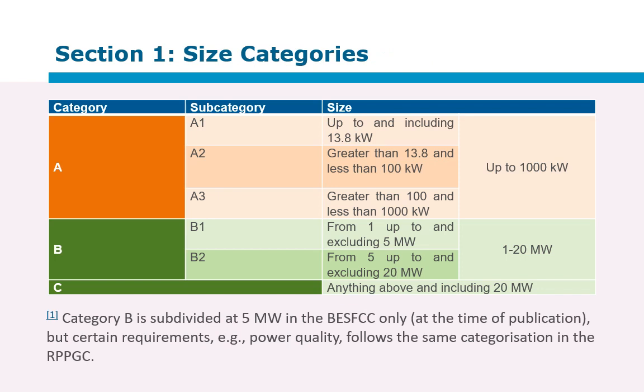Next are the size categories as defined in the grid code for renewable power plants. Category A, up to 1 megawatt, is covered by the standard SSEG processes covered in previous trainings. Many of the technical requirements are dealt with in the NRS 097-2 series of documents. The focus of the current training is to consider plants above 1 megawatt, in other words, category B and C.